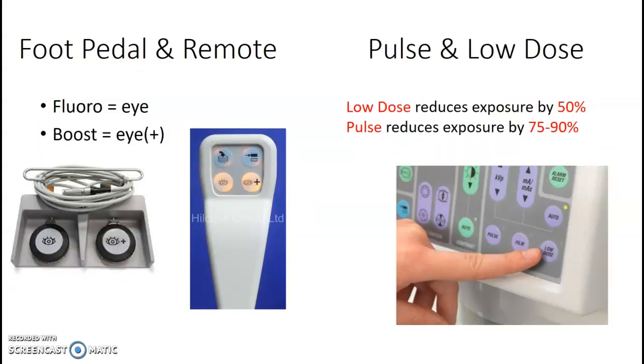Ways to make the exposure, you have a few ways. There's an exposure button on top of the C-arm that we use all the time, but you also have the remote and the foot pedal as well. The icon for fluoro is this I right here, and then boost, that higher dose fluoro, has the plus. The boost will have an extra audible beep. So if you're hearing a double beep and your surgeon has the foot pedal, they're most likely hitting the boost, so you may need to ask them to hit the other pedal, okay?